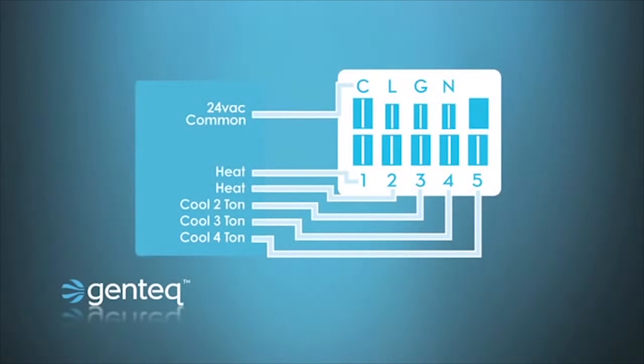And finally, we see an example of a furnace application. We see that there are 2 heat taps and 3 cool taps. The 3 cool taps being for whatever tonnage of air conditioner you're going to connect to this furnace, in this case 2, 3, or 4 ton. And we also notice that all 5 taps are programmed. So there is the potential that all 5 taps will be programmed.